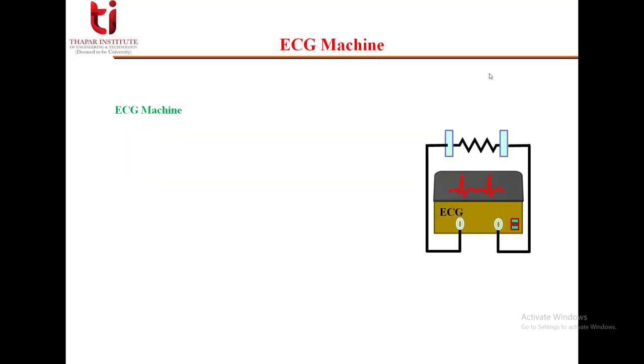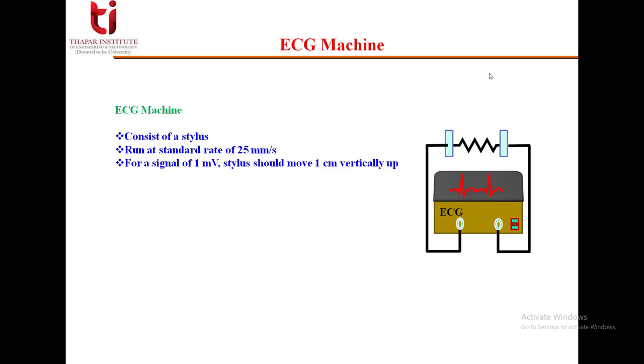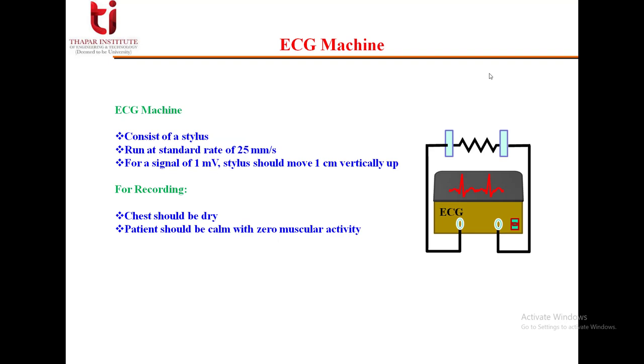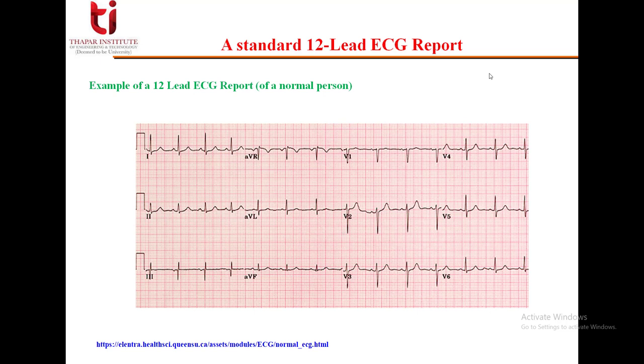For the recording part of the ECG signal, the ECG machine uses a stylus that runs at a standard rate of 25 mm per second. For a signal of 1 mV, the stylus should move 1 cm vertically. For recording, the chest should be dry and the patient should be calm with zero muscular activity; otherwise, it will contribute to artifact.